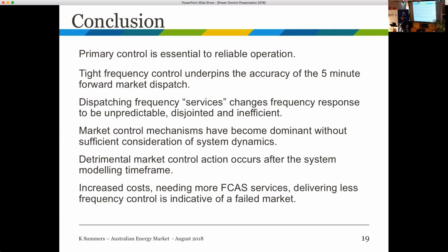They analysed the effect of the 5-minute dispatch, and they did find that the 5-minute dispatch actually causes an increase in the frequency error. So this means we have an energy market that is causing costs in the frequency control market, while we are blaming renewable energy and loads. A lot of people say, oh, it's the loads doing it. But by definition, the loads always equal the sum of the generation. And the loads have to take what they get. And if they're getting sped up and slowed down as a result of the frequency changing, they don't even know it.